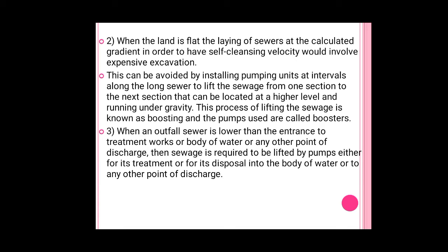When the land is flat, the laying of the sewers at the calculated gradient in order to have self-cleansing velocity would involve expensive excavation. Second, this can be avoided by installing pumping units at intervals along the long sewer to lift the sewage from one section to the next section that can be located at the higher level and running under gravity. This process of lifting the sewage is known as boosting, and the pumps used are called boosters.